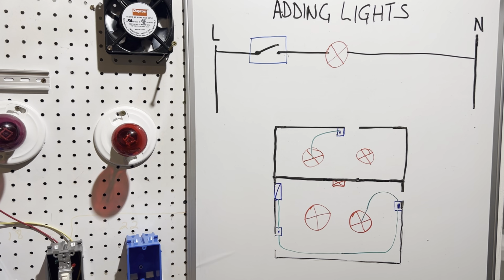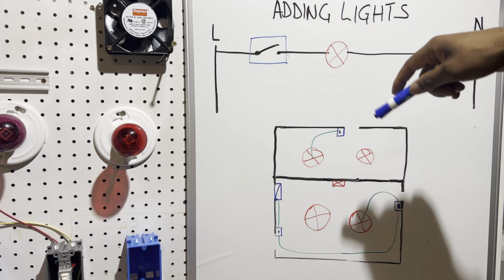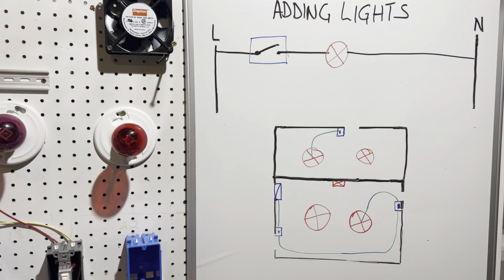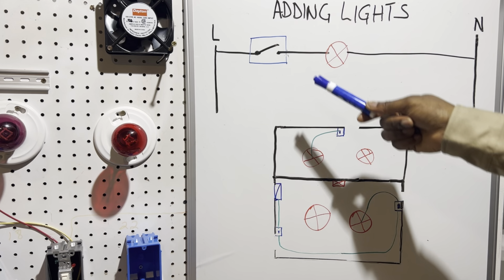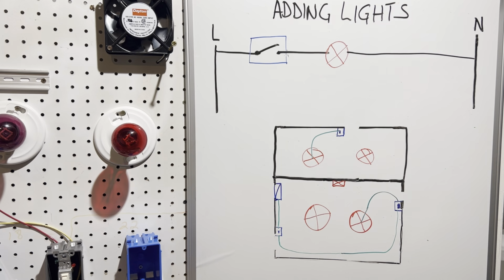So you will find some when doing lighting, especially when you're using a multiple conductor cable, you find out the white can be a phase, red can be a phase, brown can be a phase, or whatever. Or brown can be a neutral, black can be a neutral, red can be a neutral, depending on what you have available, or depending on what was available when the electrician was busy installing those lights. So it is very important. Always go to your light, because your light always has a neutral there. So that's the major thing.